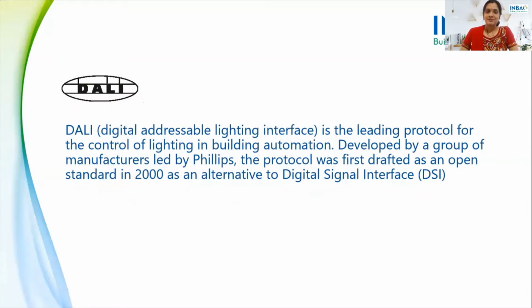DALI, Digital Addressable Lighting Interface, is the leading protocol for the control of lighting in building automation. Developed by a group of manufacturers led by Philips, it was first drafted as an open standard in the year 2000 as an alternative to Digital Signal Interface (DSI). DALI provides exceptionally fine-grained control over lighting, with each device separately addressable. 256 levels of brightness are possible, and features available under DALI include remote control, integration with fire and emergency lighting systems, balancing of light output as LEDs, and the ability to adjust lighting load based on electricity demand.